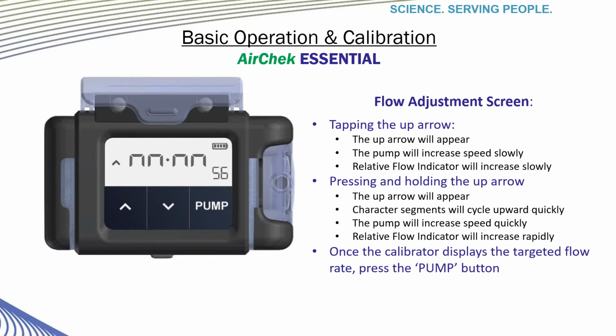Pressing and holding the up arrow down would cause the up arrow to appear at the left the same way, but this series of characters that you see on the screen would all continue upward until they go off the screen above, and then they would reappear in the bottom and continue cycling upwards over and over until you release the button. The pump would increase speed quickly in this case, and the relative flow value would increase rapidly as well. Once your calibrator has reached the target flow rate, press the pump button to continue.